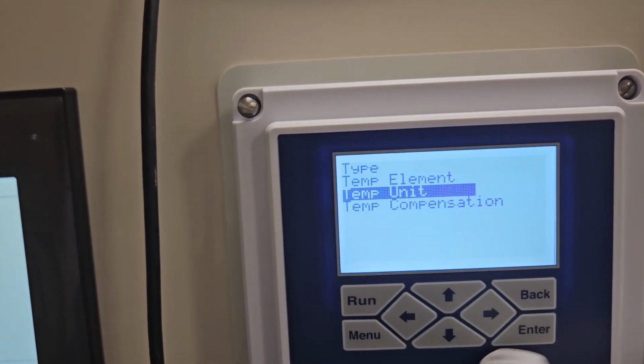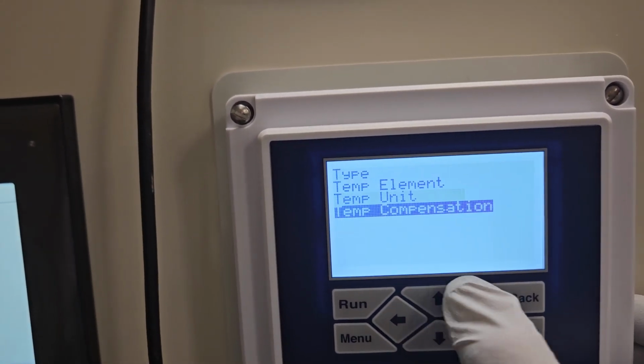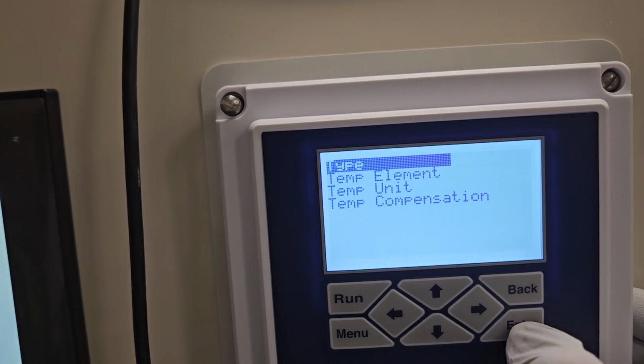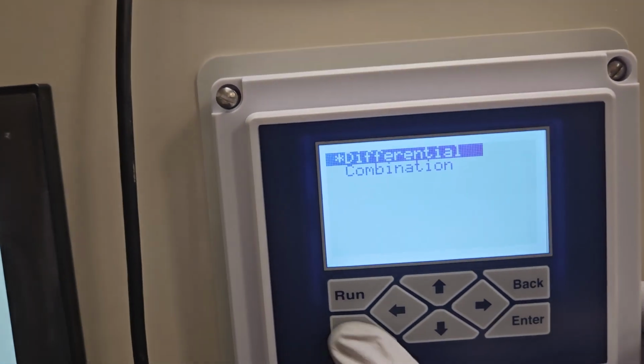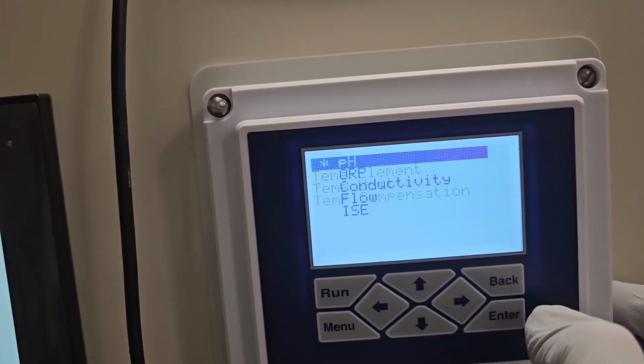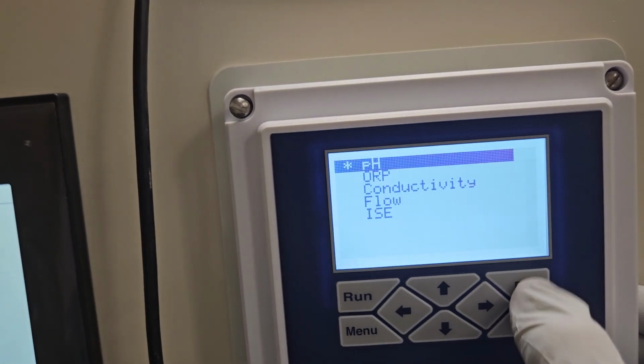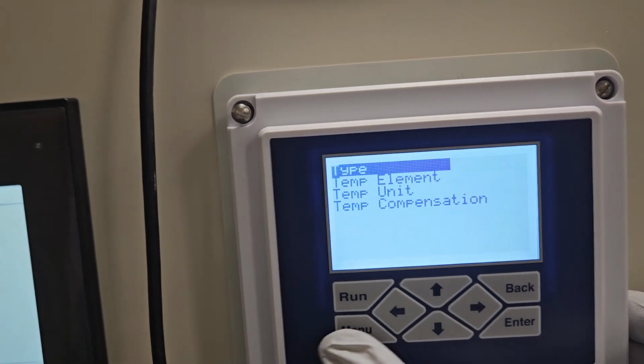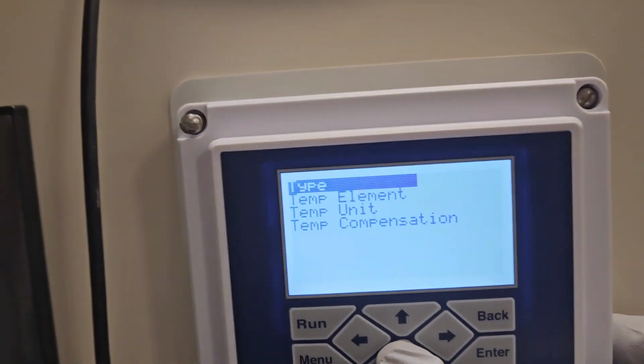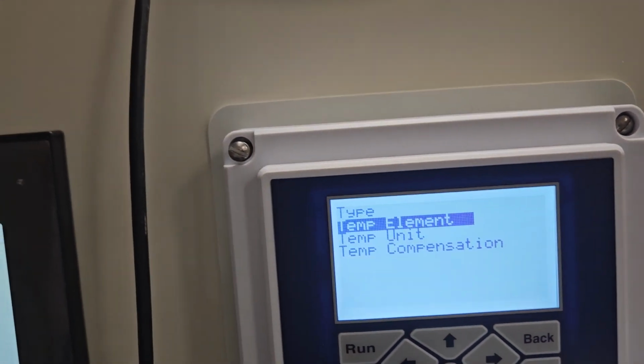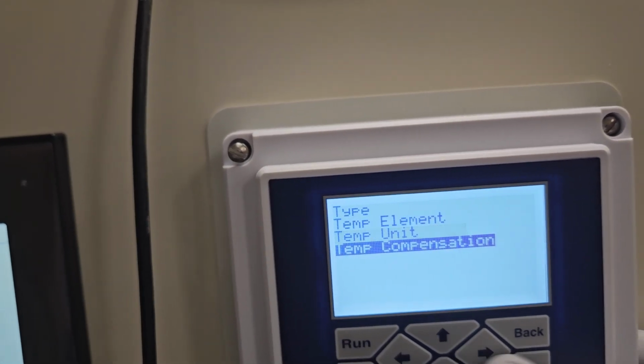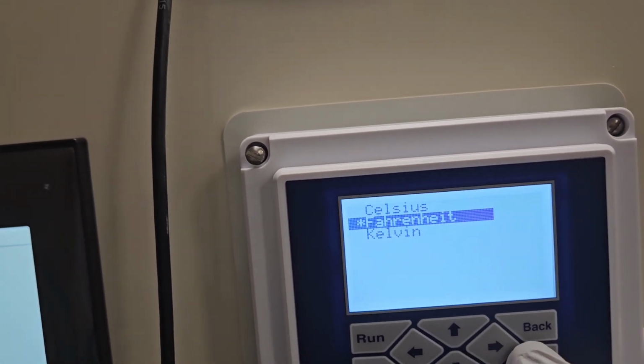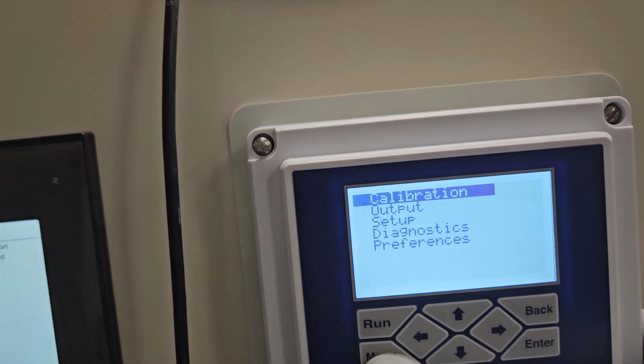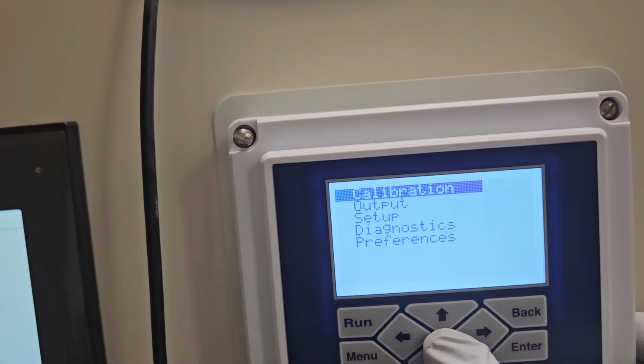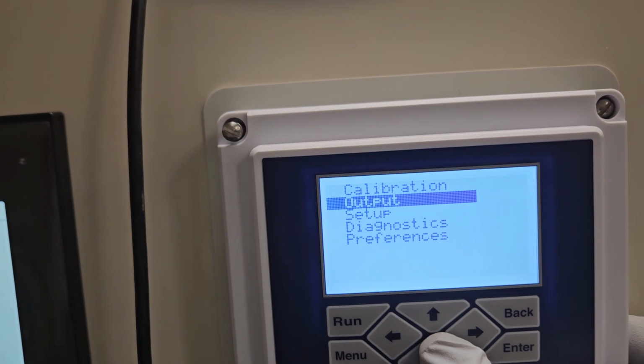So that does the type. It's finished in differential, so we can go back, and back. So that's the probe, and then the probe configuration. If we want anything, type, element, compensation, Fahrenheit, yeah, it's all the same. So this is back. Now we can go and set up the relay outputs.